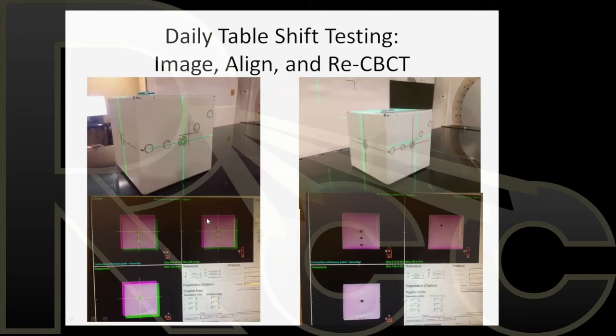So here's the first image here, used as a reference image. You can see how it's not aligned. And then finally do a table shift to that point, go in the room, check your lasers, and see that they are on the off-axis point. And then re-image it, and this should be in perfect alignment. So you can use one phantom like this to do a number of different tests.